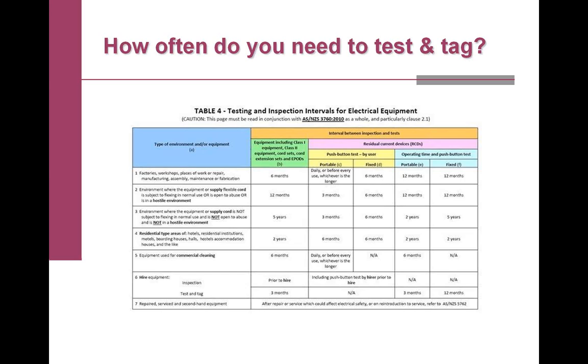A good example from a printing industry perspective would be a showroom or area where you bring clients in, with equipment that customers and staff would be handling — that's somewhere you'd want to test 12 monthly to be safe. Whereas your pre-press area out the back, you might test every 5 years, because it's only your staff, computers sitting under desks, not likely to be subject to dust, moisture, or vibration.